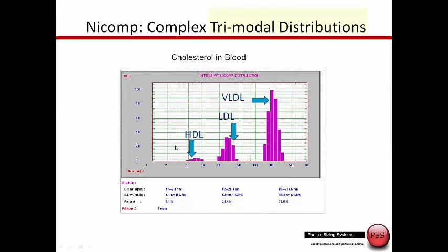This slide actually shows our ability to resolve three separate peaks using the NICOMP algorithm. This is cholesterol in blood and cholesterol has three components: HDL, LDL, and VLDL. This shows our ability to resolve these three peaks that are fairly close to each other and is a unique capability of the NICOMP DLS system.